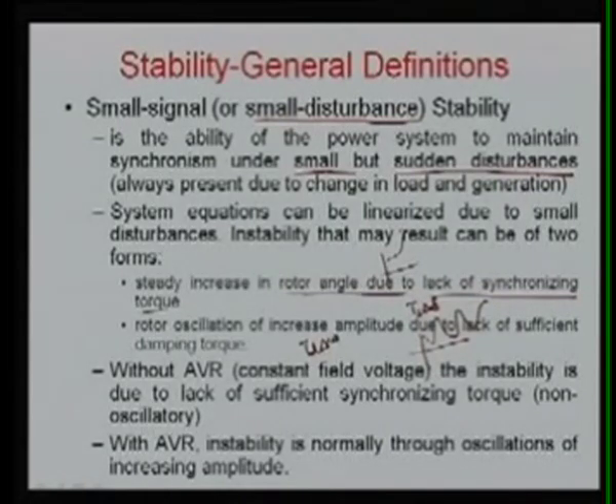Normally the first one, without AVR, with constant field voltage, the instability is due to lack of sufficient synchronizing torque. So, as I said, the lack of synchronizing torque will give aperiodic drift of the rotor angle if there is no AVR, automatic voltage regulators. But nowadays modern power systems have automatic voltage regulators, so that type of instability is normally not happening. So only small signal stability is of concern, and we always go for the oscillatory type of instability that appears with the AVR, that is, the automatic voltage regulators, means the excitation system. Automatic voltage regulation means we have to control the voltage automatically, and that is basically due to the excitation system that is available with the generators.